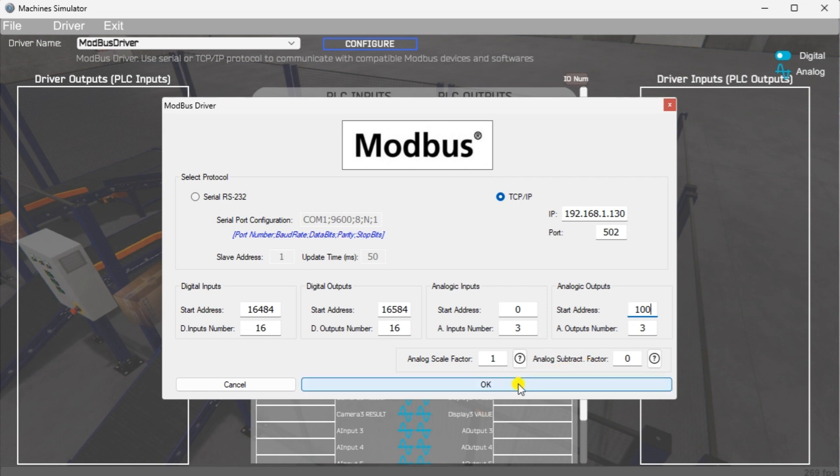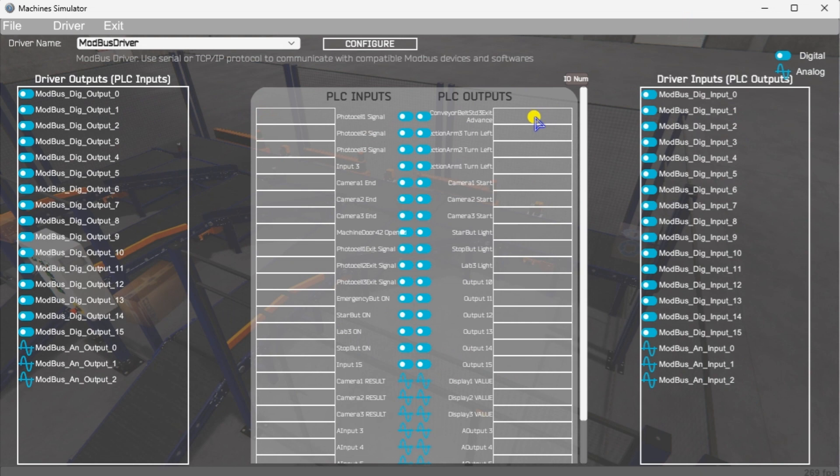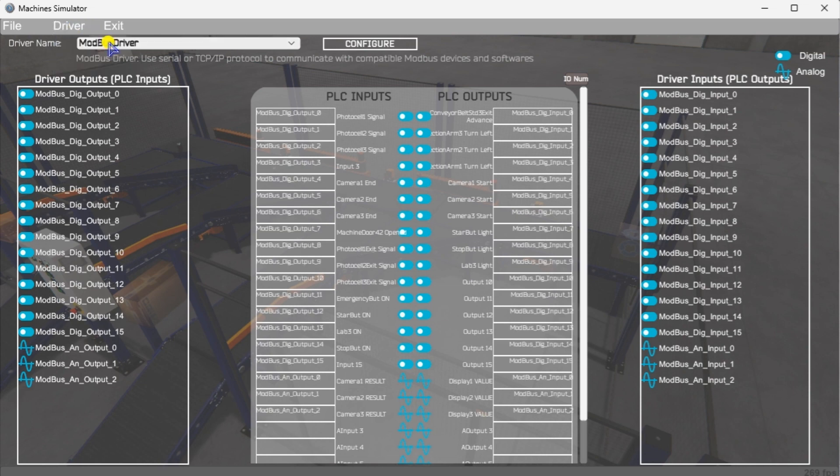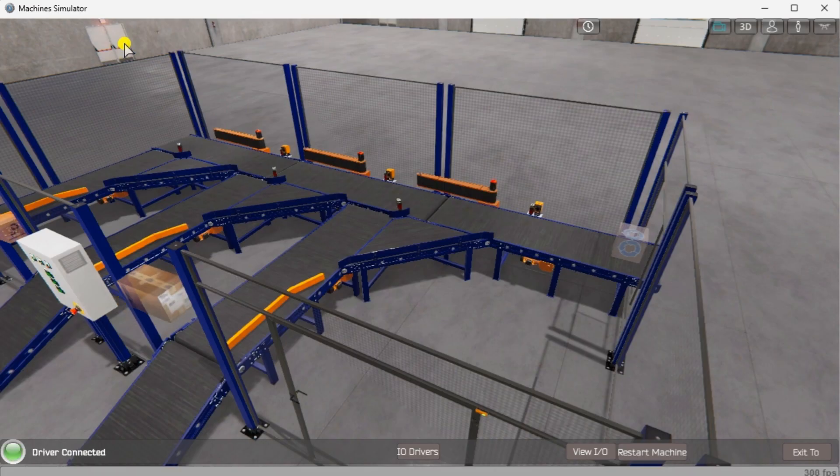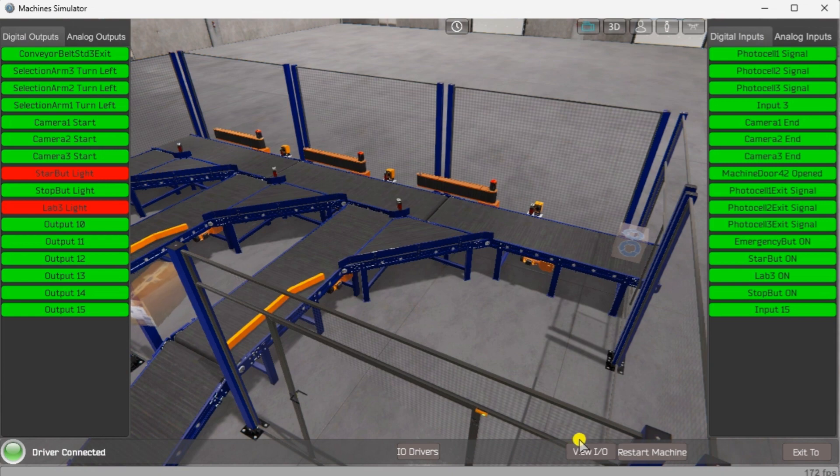Select the OK button. You can now see the inputs and outputs specified for the Modbus driver. We can now manually assign the driver outputs to the PLC inputs and the driver inputs to the PLC outputs. However, an automatic assignment will do this if the IO is in the same order in the PLC and Easy PLC Machine Simulator. Select automatic assignment from the driver option in the main menu. This will automatically assign the PLC IO to the Machine Simulator IO. Select Start Driver and Exit from the main menu under Exit. You will see that the driver is operating on the bottom left side of the window. Select View IO to know the input and output status of the Machine Simulator.